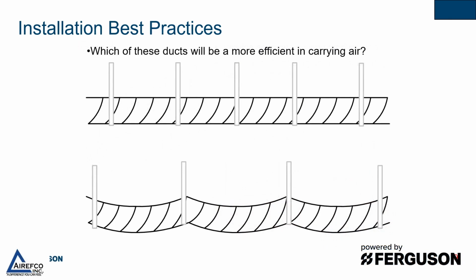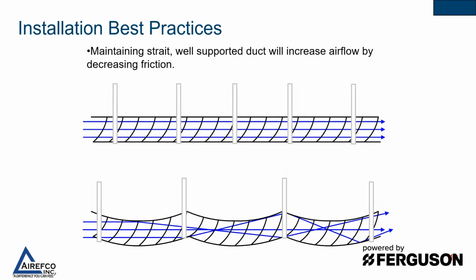So which of these ducts will be more efficient in carrying air throughout the system? If you pick the top one, you are correct. Maintaining straight and well-supported duct will increase airflow by decreasing the friction. The ductwork as run in the diagram below shows how much turbulence can be caused by not running the flex duct correctly. So make sure when you're running the flex duct that it's supported the way that it's supposed to be and that it is stretched out fully so that the air will flow freely through it and there will be no restrictions and no turbulence that will cause lack of airflow.